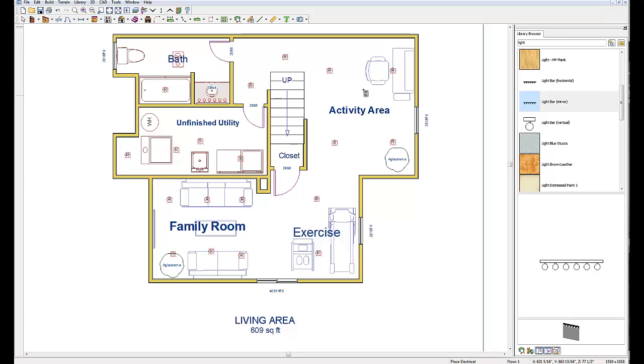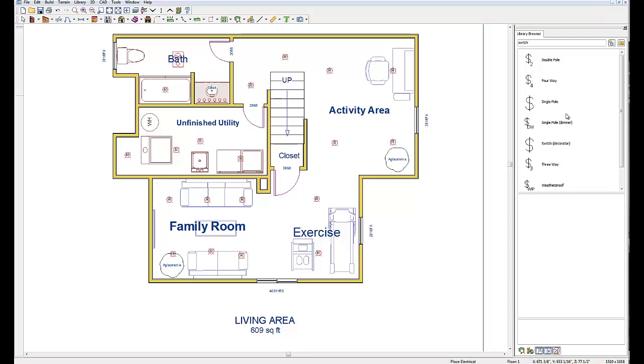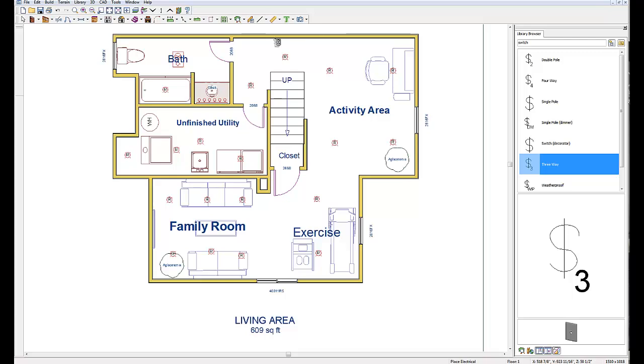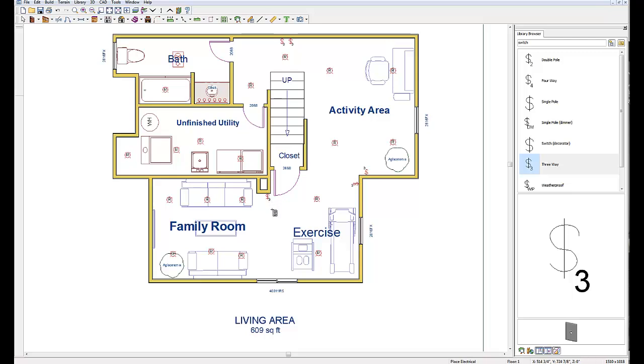The next thing I have to do is put my switches in. I'm going to type 'switch' in the library browser. I'll be using a combination of three-way switches — which turn a light or group of lights on from two different locations — and single-pole switches, which turn a light on from one location. Starting with three-way switches: I know I'm going to need two at the bottom of the stairs, another one in the activity area, one around the corner in the exercise area, one on this column, another three-way there, and one at the top of the stairs.